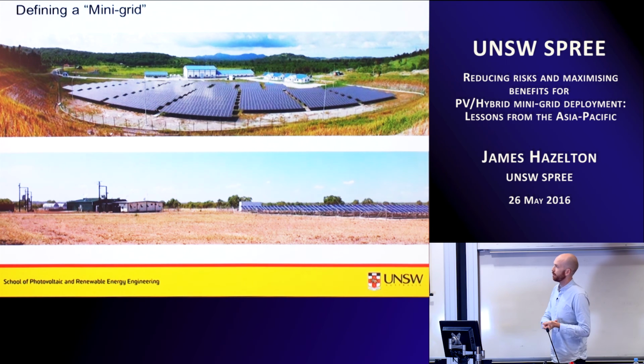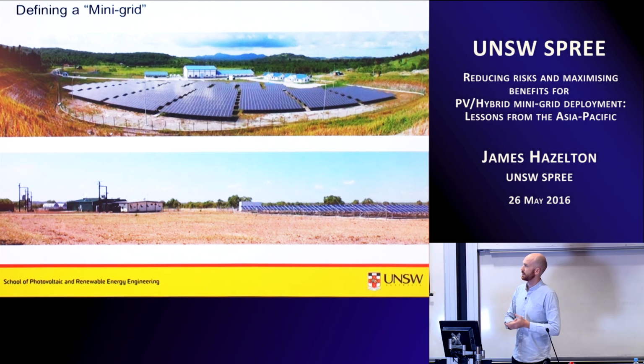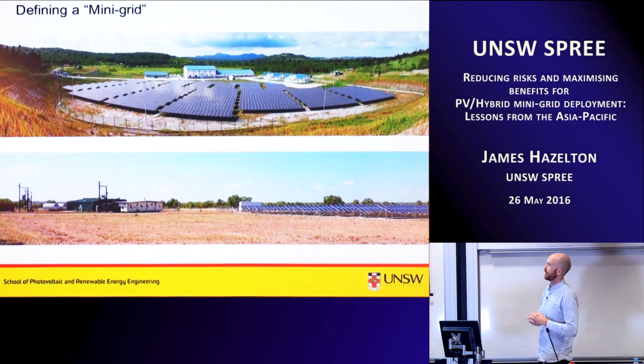This is 1.1 megawatts of solar connected to a standalone mini-grid system. In the tall hut there are 5 diesel generators between 400 and 200 kilowatts each, which run individually rather than simultaneously. On the right of that tall hut is a large battery room with 3 megawatt hours of installed capacity, and on the left you'll see the diesel fuel tanks.